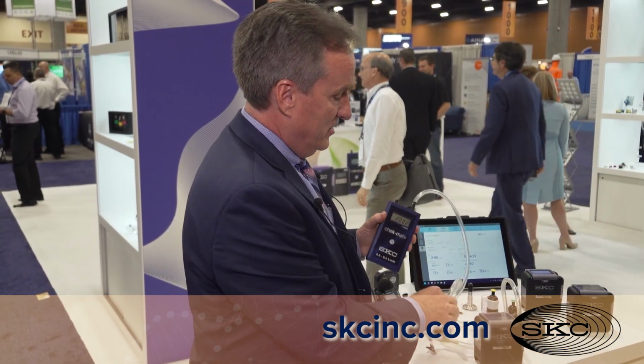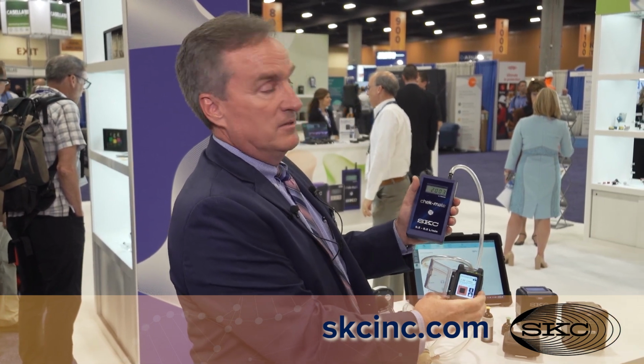Last and certainly not least is our calibrator that's created for air sampling pumps. It meets all of OSHA's guidelines as far as NIST traceability and accuracy standards, and as you can see on the display, it's real time. So it doesn't matter if it's right side up or upside down, and it operates off a 9-volt battery, and depending on how often you use it, you could get up to a year and a half use out of a 9-volt battery. And as I mentioned earlier, it gives you the opportunity to match the display on the pump with what the calibrator is reading. So you're not just checking your flow rate, you're actually calibrating the pump to give you the accurate flow rate.